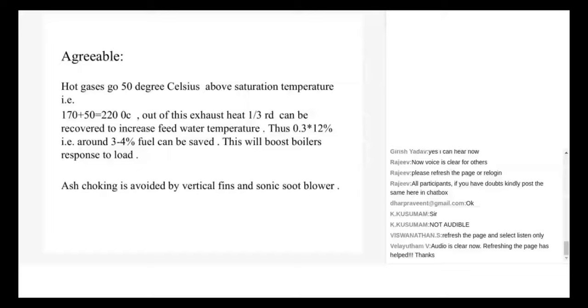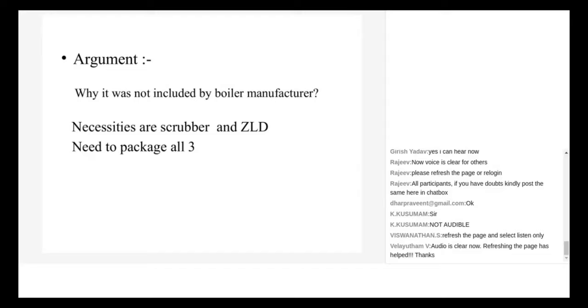Otherwise, the typical problem is you put the equipment, then for 2 or 3 months it runs fine, then it gets choked. After choking, his worry is not about loss in efficiency—the choking or any small cross section starts throttling his boiler's burning capability, and he cannot produce the steam he used to generate. So then he will throw it off. He doesn't even care about what happens to the investment.